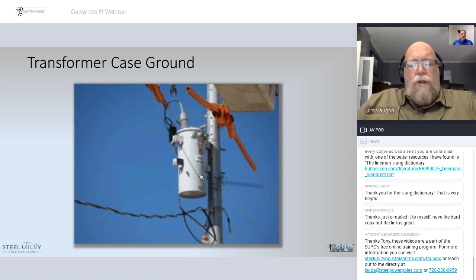If you lose that connection, then the grounding of the tank occurs through the hangers to the pole. On a wood pole, and here's a big benefit for steel poles because we've already seen this, there's a very high resistance between this mechanical hanger on the bolt into the wood pole. And when you lose this connection, or it vibrates loose, or it breaks, or whatever happens, this bolt becomes very hot and will actually set the pole on fire. In my career, I've done trouble calls and come out and actually found the whole center of the pole burned out and the transformer barely hanging on the bolt.